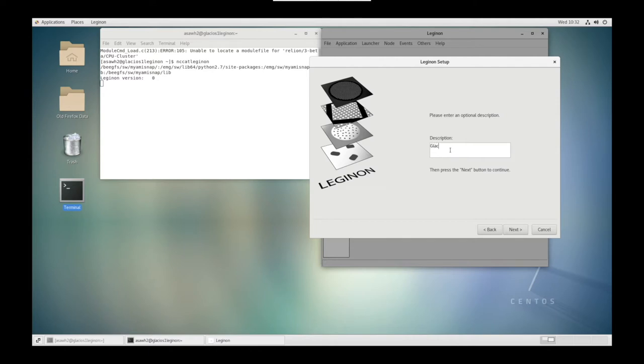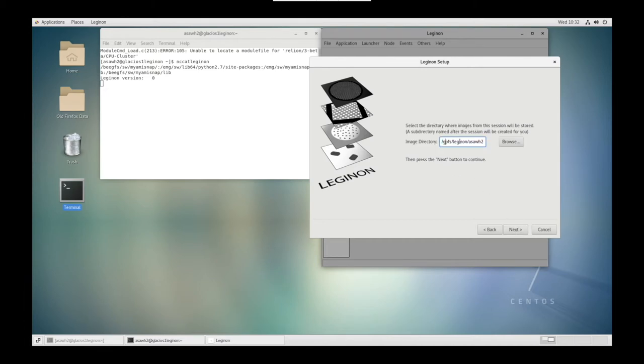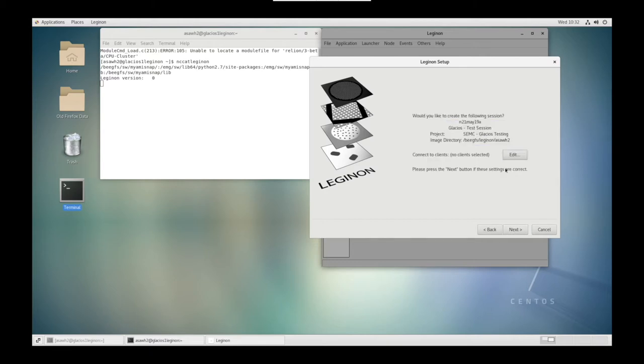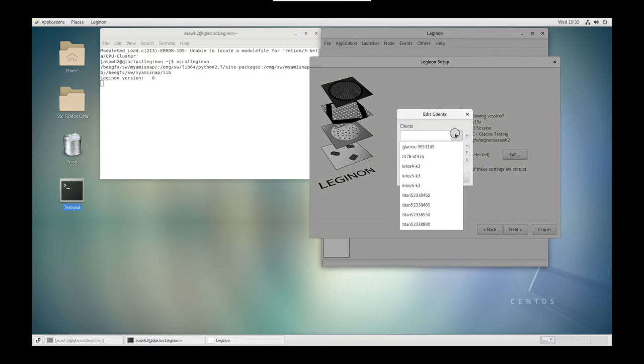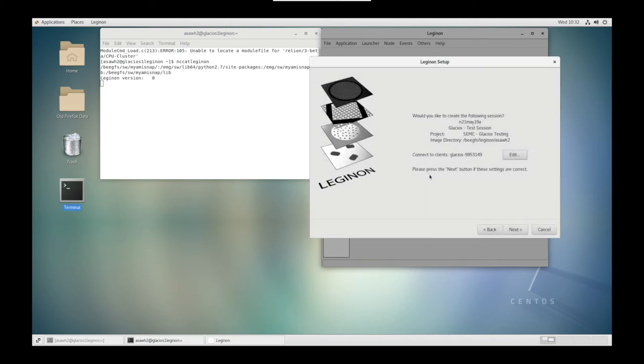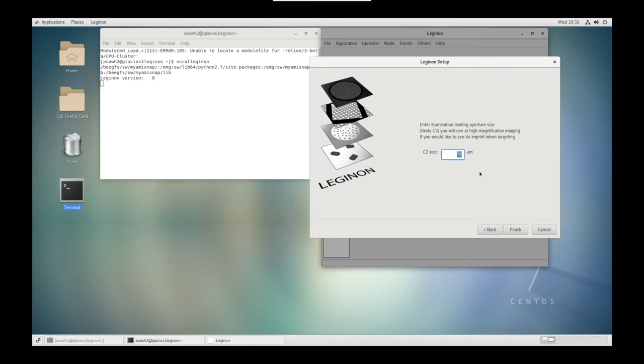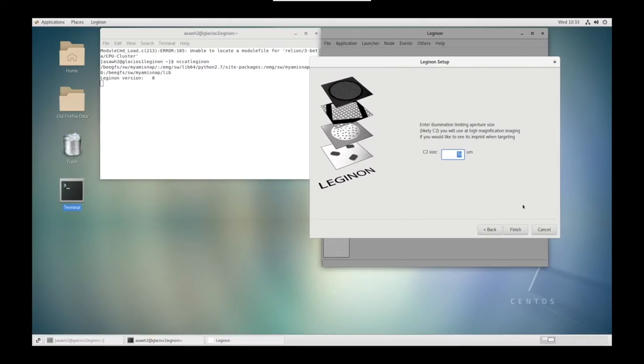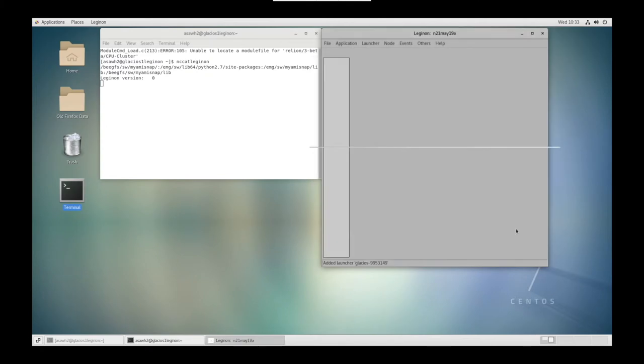In the description, we can put Glacios and you can name it whatever you'd like. Next, the image directory. Make sure that it says BEEGFS slash Leginon slash your LDAP account. Next, connect to clients. Add client Glacios 995-3149. Select OK, then Next. Our C2 Aperture is going to be 70 microns. We can double check that in the Apertures on the Microscope PC. Select Finish.